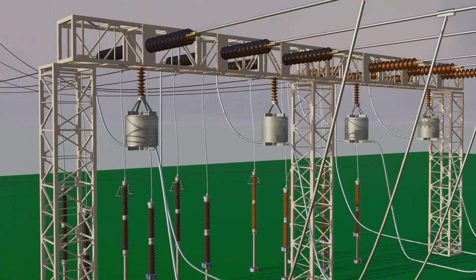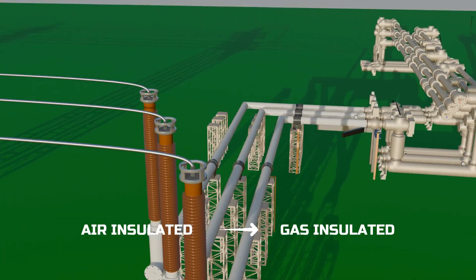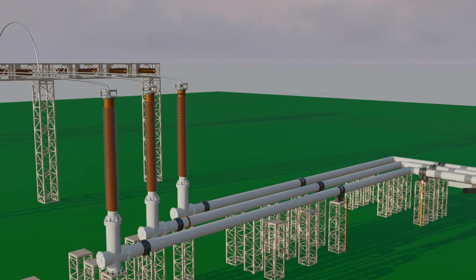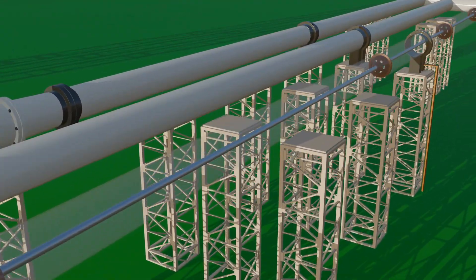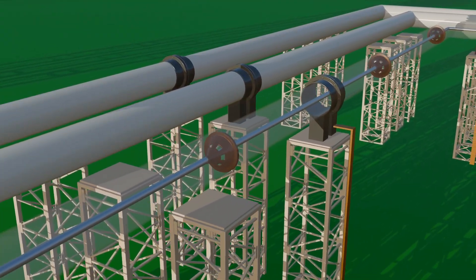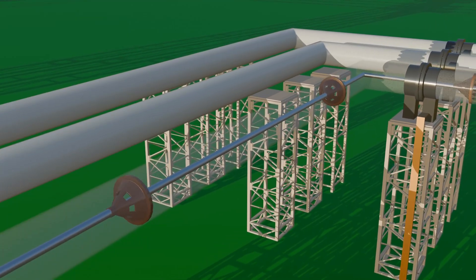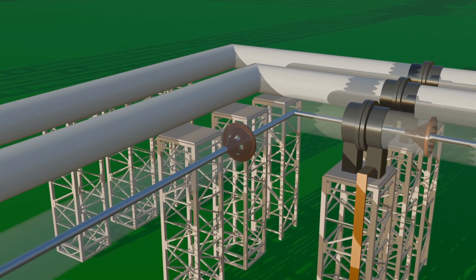Up to this point, all components were air insulated. From here the line enters a gas insulated bushing. Below these bushings are large cylindrical pipes which are hollow from the inside. Inside these pipes runs a solid conductor, commonly called the bus conductor.